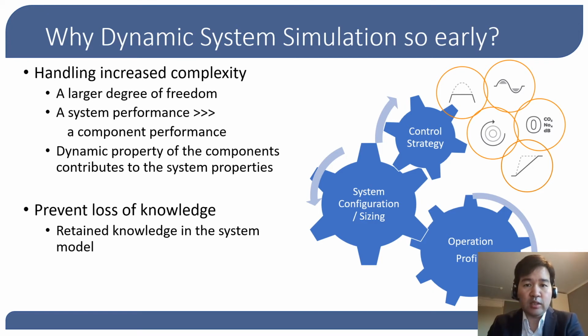A challenge is that these operations will not always save energy, but may do the opposite. A proper control strategy with correctly sized machinery under a specific operation profile will maximize the benefit of the novel technology. Here, system performance is our key interest, rather than best performing components. In addition, we need to take into account the dynamic properties of components, primarily the battery, to evaluate system performance. When to charge or discharge, or how fast, combined will result in better or worse performance.